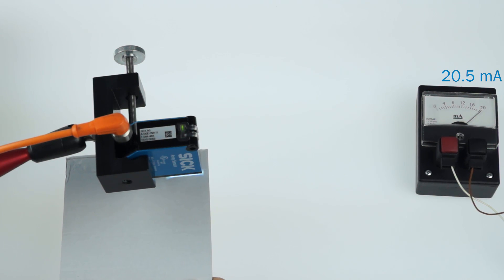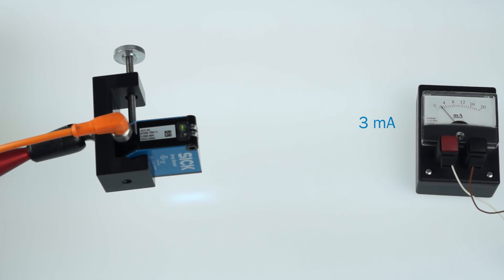If the material leaves on the opposite side, a value of 20.5 mA is shown. If a sudden signal loss occurs, which may happen with a web break or if the sensor has no orientation, the sensor displays 3 mA.